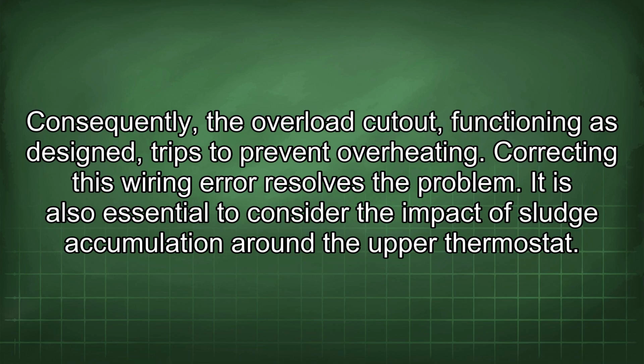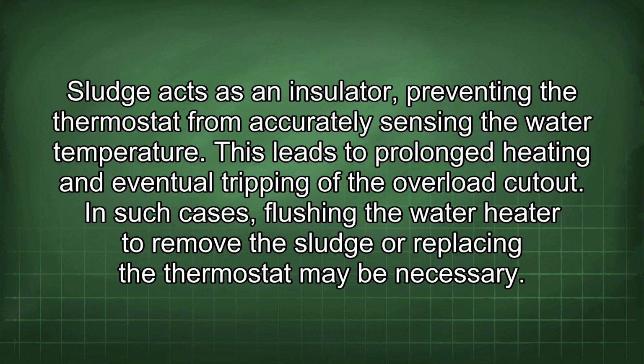It is also essential to consider the impact of sludge accumulation around the upper thermostat. Sludge acts as an insulator, preventing the thermostat from accurately sensing the water temperature. This leads to prolonged heating and eventual tripping of the overload cutout. In such cases, flushing the water heater to remove the sludge or replacing the thermostat may be necessary.